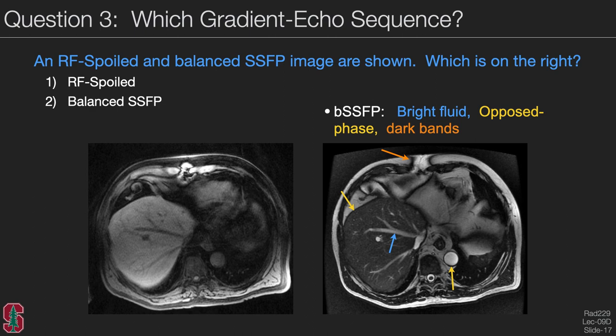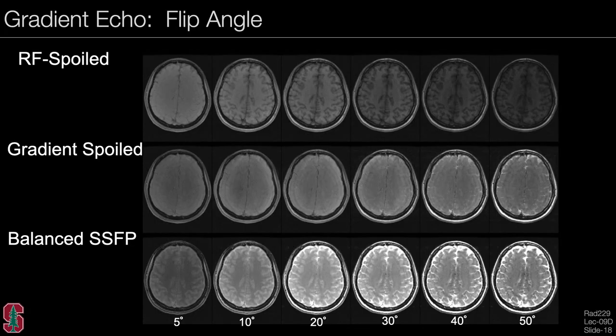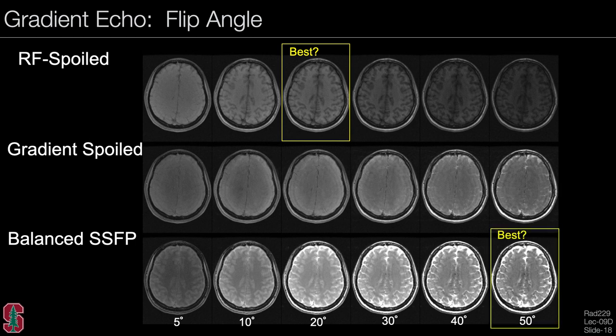The main key thing to recognize is simply the image contrast. Looking at signal as a function of flip angle for the three main spoiling methods, the signal is low for a very low flip angle, peaks at some flip angle, then drops again. Choosing the best flip angle is a combination of signal-to-noise ratio and contrast, and is somewhat empirical.